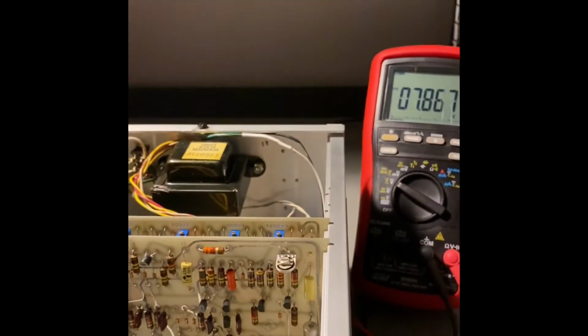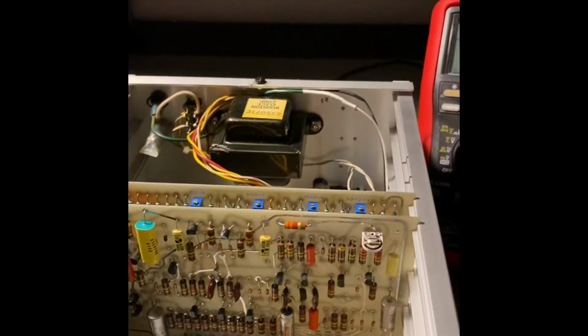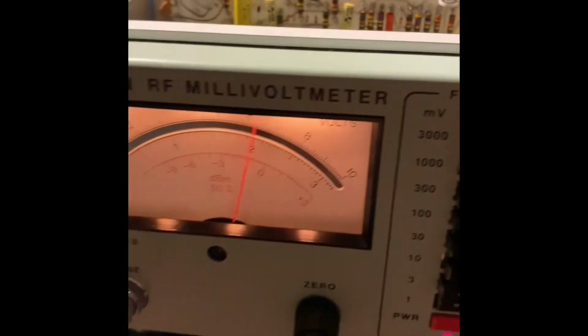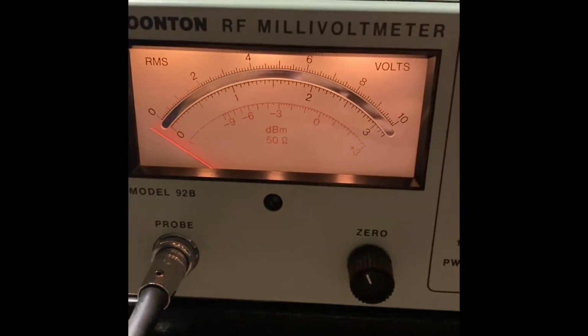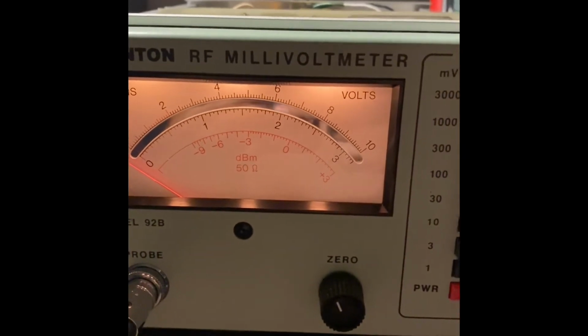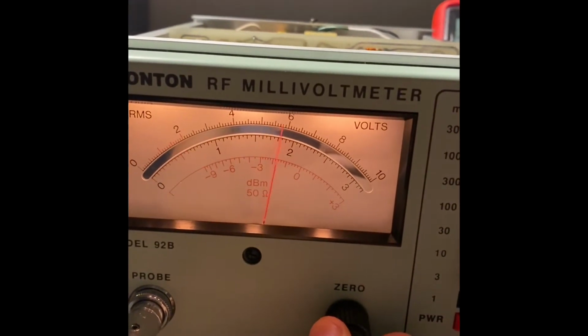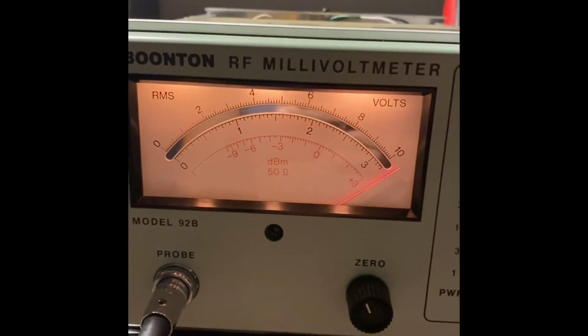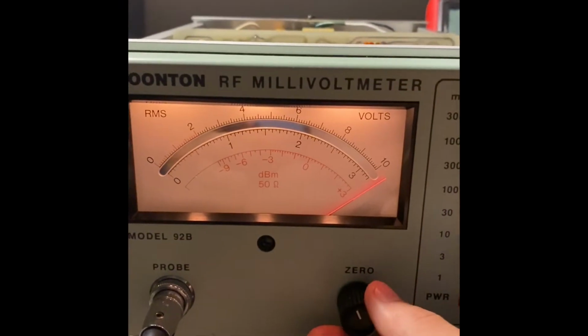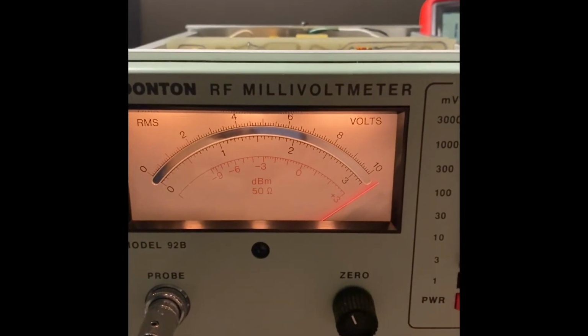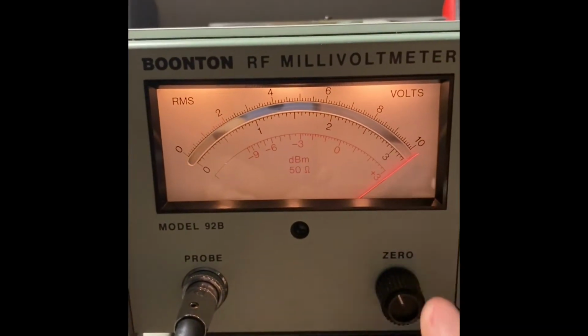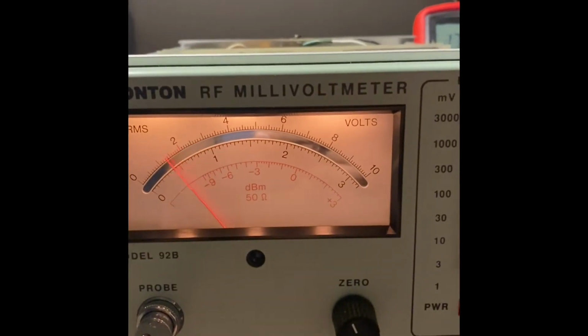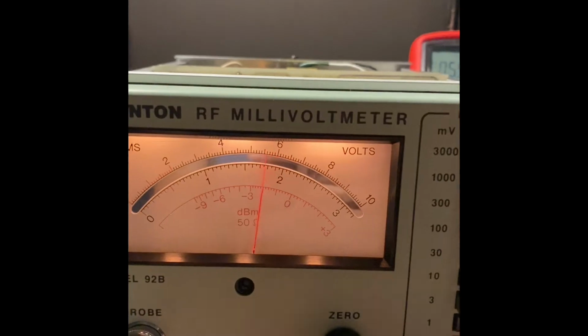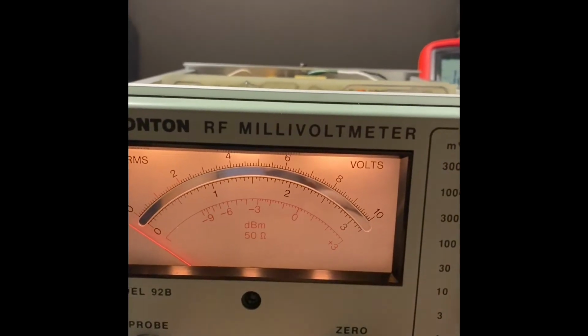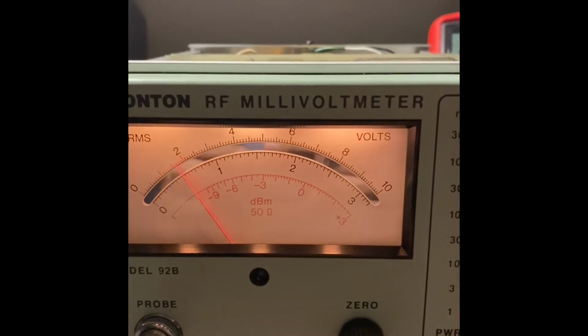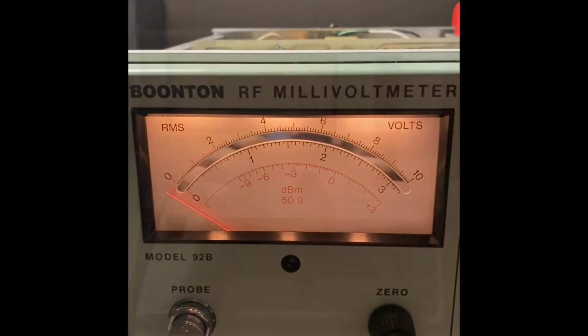So now I'm just trying to zero the instruments, but as you can see I have some, I don't know, it picks up something, so it jumps around sometimes, as you can see. I don't know why. I still have to figure out the reason for this. So when it's difficult or basically impossible to zero the instrument, then it's also difficult to calibrate the scale. So I'll try and see if I can do this off camera and then come back with the results.